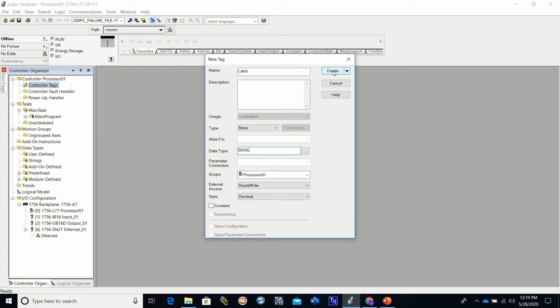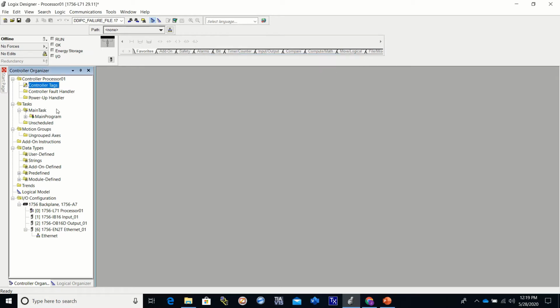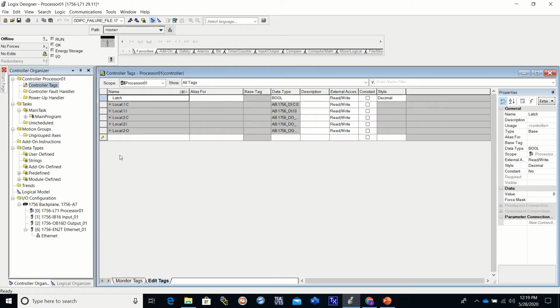I'm going to open my controller tags, and you can see that it is right here. Now, in the last video, we set up an input card and an output card, and you can see these right here. Since we set up our input card in slot number one, the Local:1:I is associated with my input card.